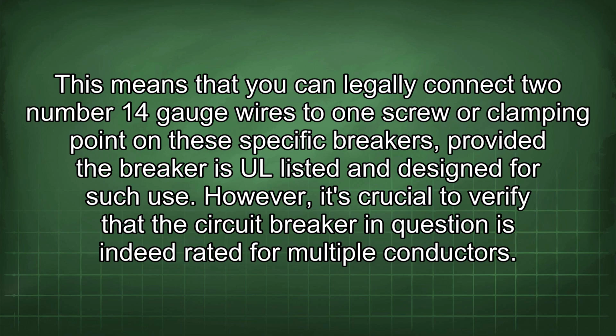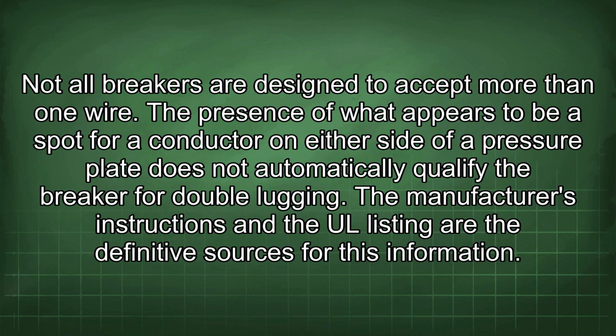However, it's crucial to verify that the circuit breaker in question is indeed rated for multiple conductors. Not all breakers are designed to accept more than one wire. The presence of what appears to be a spot for a conductor on either side of a pressure plate does not automatically qualify the breaker for double lugging. The manufacturer's instructions and the UL listing are the definitive sources for this information.